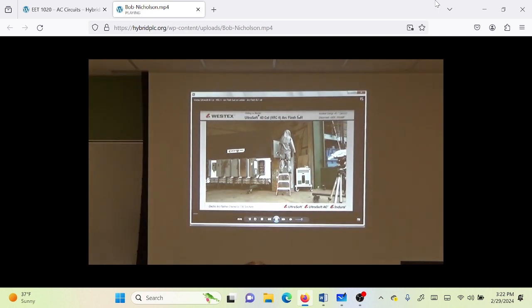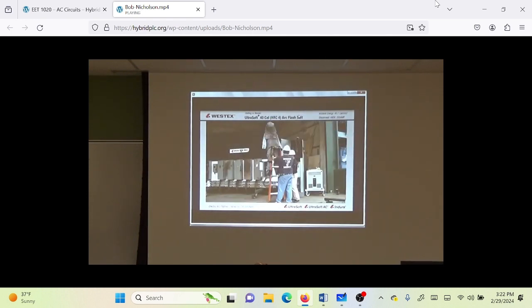This mannequin is wearing a Westex Ultrasoft 40 calorie flash suit, and he's up on the ladder, because this is what happens if an electrician's up the ladder. So we're faulting the upper bucket of the motor control center. It's a 45.7 calorie arc. It's a very large arc. There's a ton of molten metal coming out in all directions, but there is no fire on the garment. When our firefighters come in and turn the mannequin around, you see that there's also no break open, showing you that even in a 45 calorie arc, the Ultrasoft provides sufficient protection.